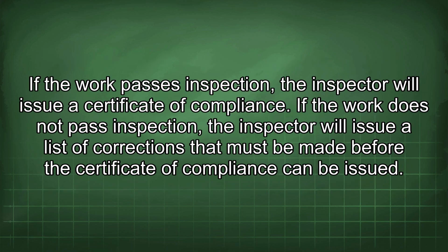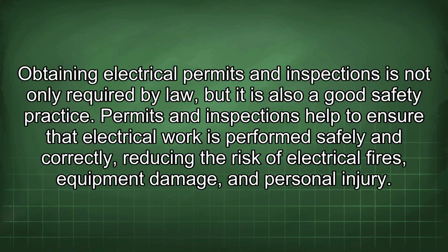If the work passes inspection, the inspector will issue a certificate of compliance. If the work does not pass inspection, the inspector will issue a list of corrections that must be made before the certificate of compliance can be issued. Obtaining electrical permits and inspections is not only required by law, but it is also a good safety practice. Permits and inspections help to ensure that electrical work is performed safely and correctly, reducing the risk of electrical fires, equipment damage, and personal injury.